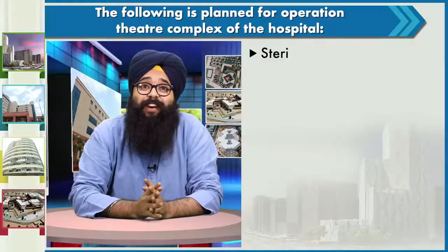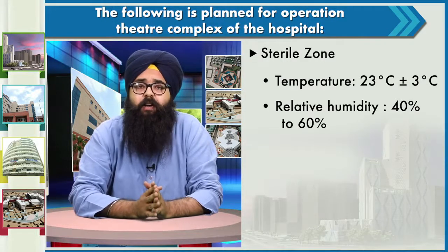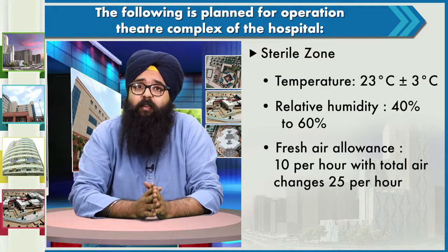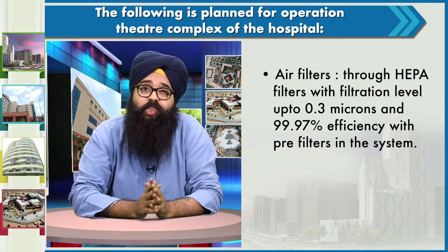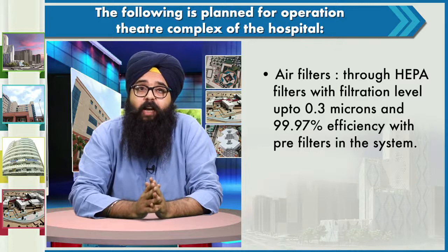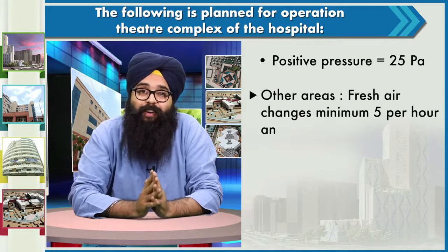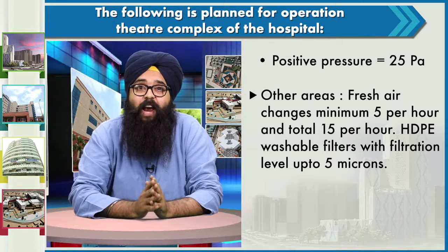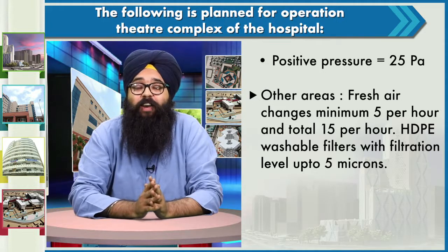We have to create a sterile zone for the operation theatre complex. Temperature should be 23°C plus or minus 3 degrees, relative humidity 40 to 60 percent, fresh air allowance of 10 air changes per hour with total air changes of 25 per hour as per ASHRAE. Air filters must be HEPA filters with filtration level up to 0.3 microns and 99.97% efficiency with pre-filters in the system, meaning even bacteria can potentially be stopped. HDPE washable filters with filtration up to 5 microns should also be provided for other areas, with a minimum of 5 fresh and 15 total air changes per hour.